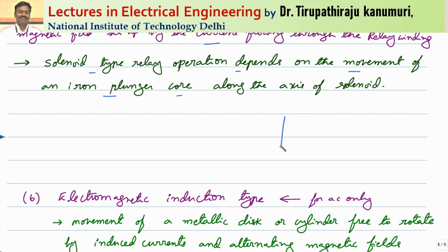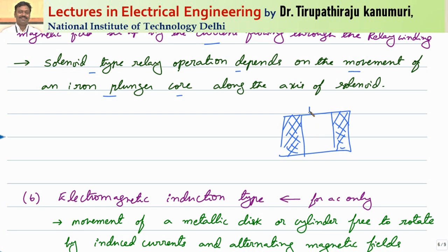The solenoid type relay operation depends on the movement of the iron plunger or core along the axis of the solenoid. In the solenoid type, there is a coil — the cross section is hollow inside, and an iron bar is placed inside. This iron bar is connected through a small bar to the contacts. Whenever the coil is energized, it produces a magnetic field that attracts this plunger inside, causing the contacts to close.